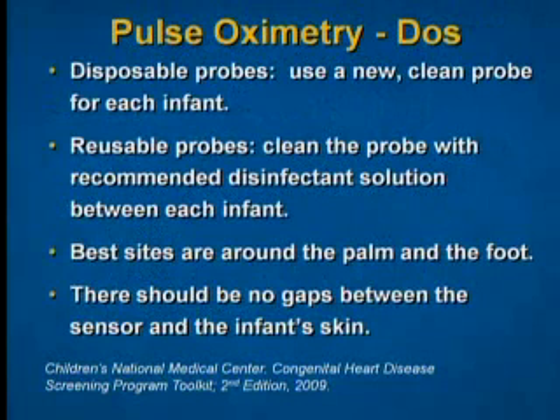And then some of the things that the screener should do when performing the pulse ox screening: if they're using disposable probes, they should be sure to use a new clean probe for each infant. And if using the reusable probes, they should be sure to clean the probe with the recommended disinfectant solution between each infant. And then again, the best sites, as Dr. Carlo mentioned, are around the palm of the right hand and either foot.